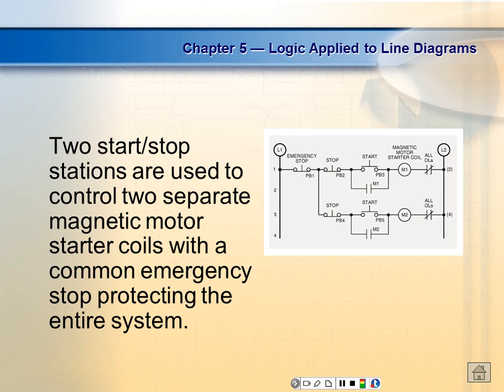And it also kills power to the control circuit, because when you press the emergency stop, if it's not defective, then what should happen? It should latch down, right? The emergency stop button should latch down, which would remove power from the control circuit too. But you don't quite see that here because it looks like just a block. Looks like just a normal closed push button. But it's a latching push button.